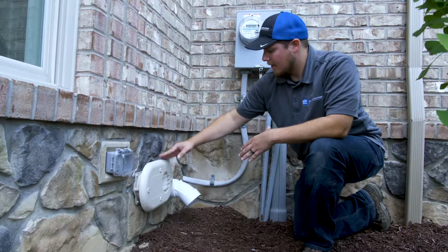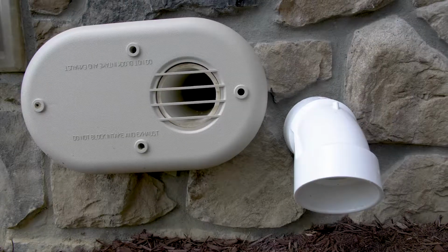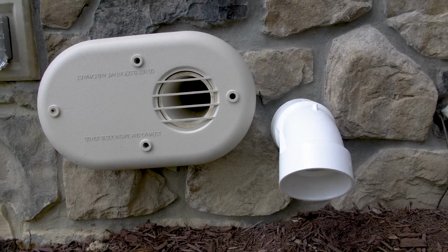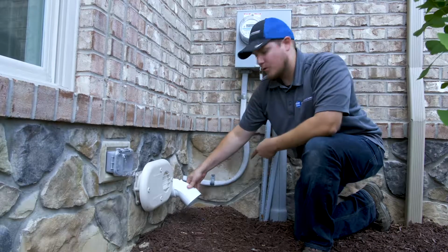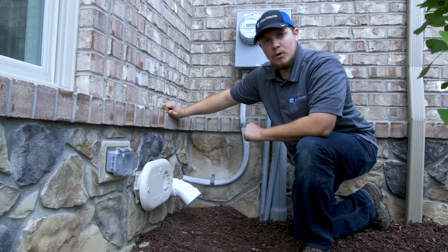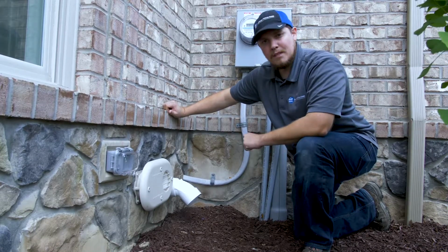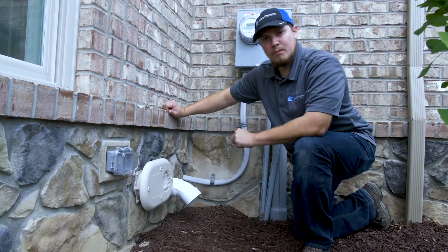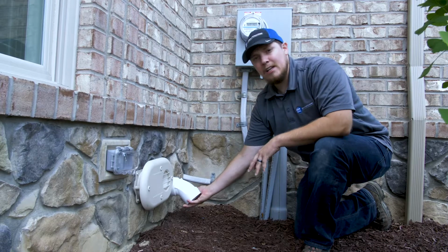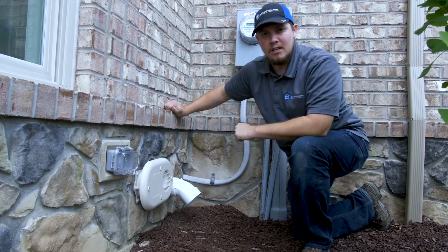As I mentioned downstairs, two main components to your HVAC system are the intake and exhaust. This is the intake here, and this is the exhaust. One important thing to know is that the combustion of natural gas naturally creates moisture. This moisture is being exhausted through the pipe here. During cold weather, that moisture that's being exhausted can sometimes create ice. If the wind's blowing from a certain angle or if the weather is really cold, that ice can build up and end up blocking your system, causing the furnace to shut down.